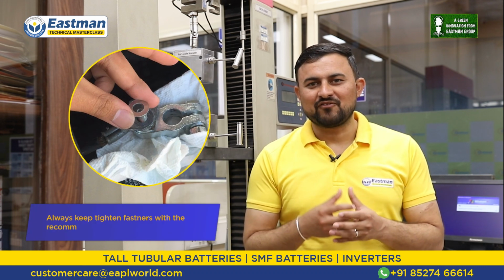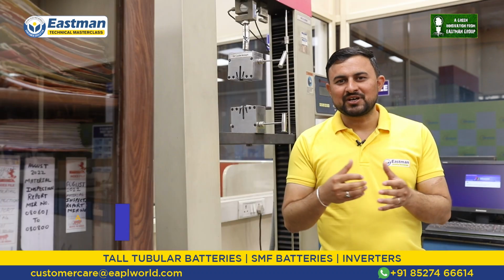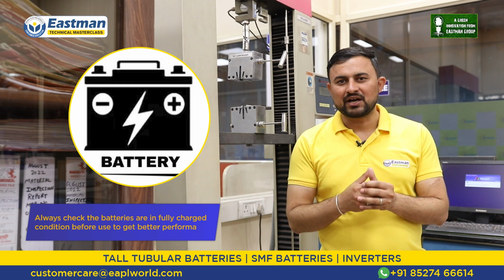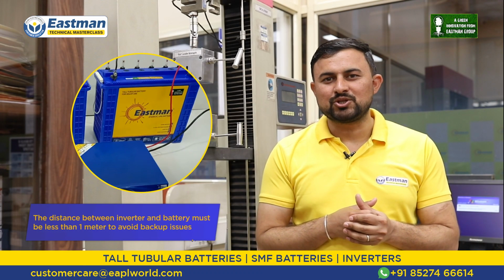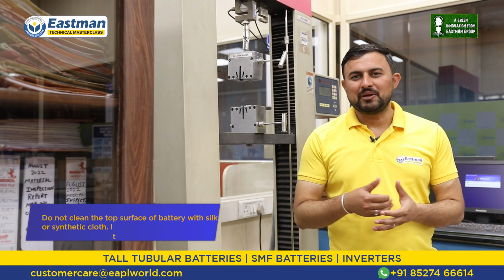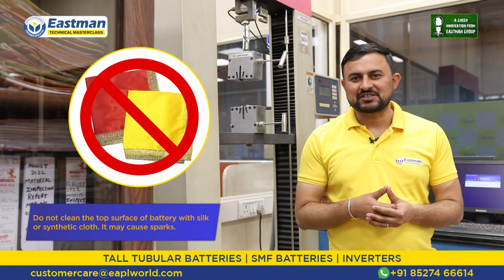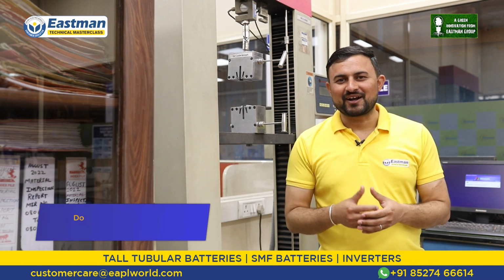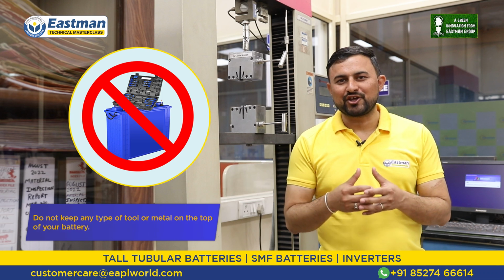Always tighten the fastener with a washer only. Before using the battery, check that the battery is fully charged so that you can get better performance from it. The distance between your inverter and battery should not be more than 1 meter. Never clean your battery with silk or synthetic cloth. There is a risk of spark in that case. Do not keep any kind of metal or tool on top of the battery.